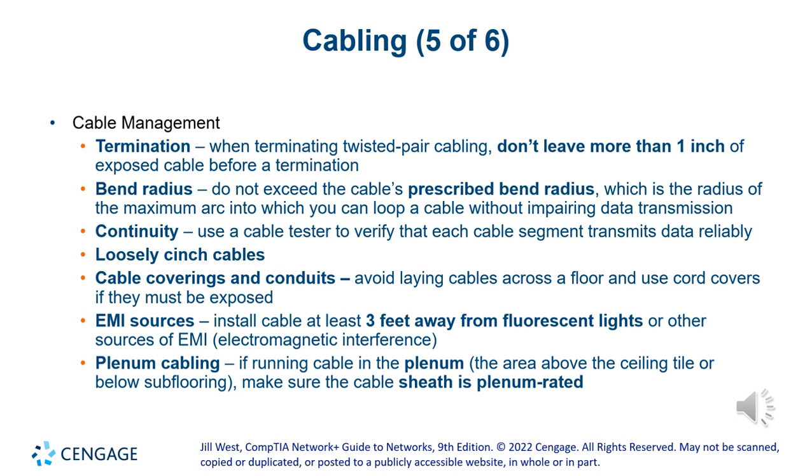And believe me, if you do that at 1.5 inches, God forbid 2 inches of exposed cable, that cable would have problems. It starts creating that crosstalk that I was telling you about, and it will create problems with your connection. It connects and disconnects. You get errors in the connection. So the cables need to be protected by that shield and all tied together, but no more than 1 inch. So when you cut your cables, you expose the cables 1 inch, and then you make the connection like that. Don't make exactly 1 inch. Try to make it as short as you can, less than 1 inch. It has to be less than 1 inch, but no more than 1 inch when you terminate the cable.